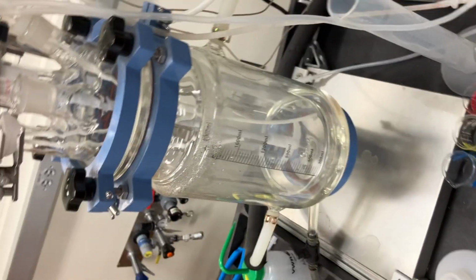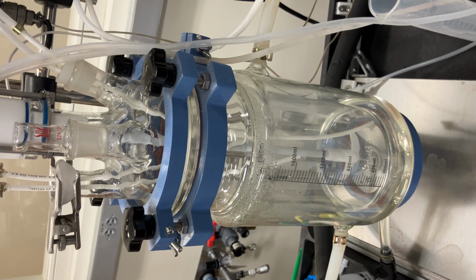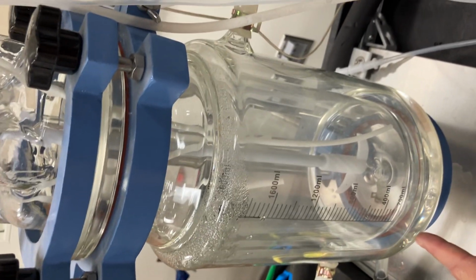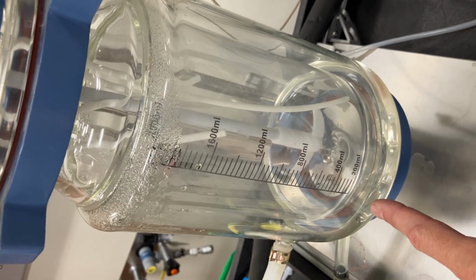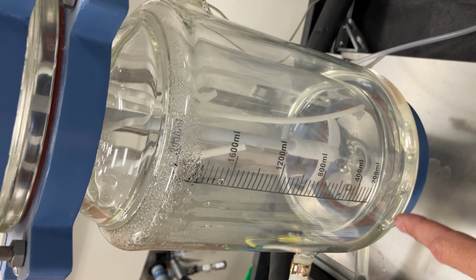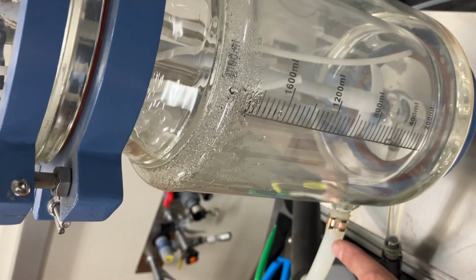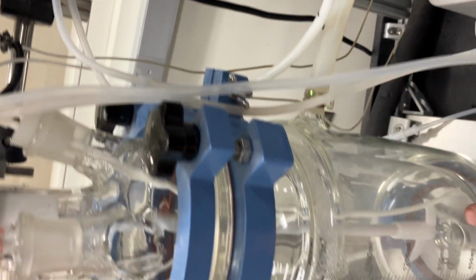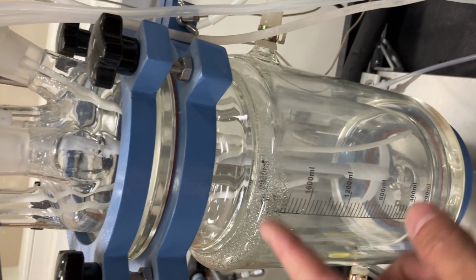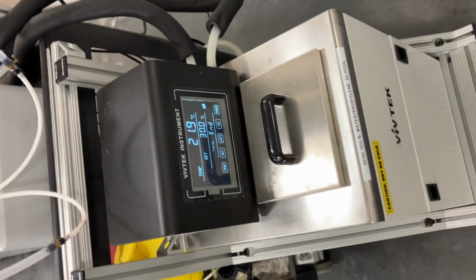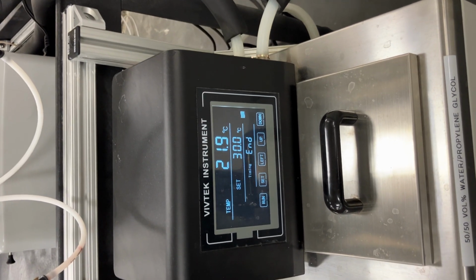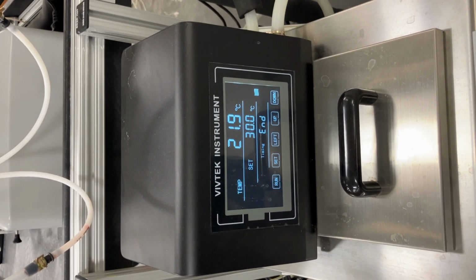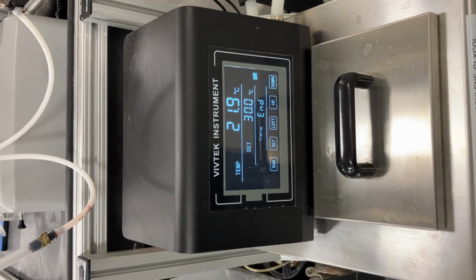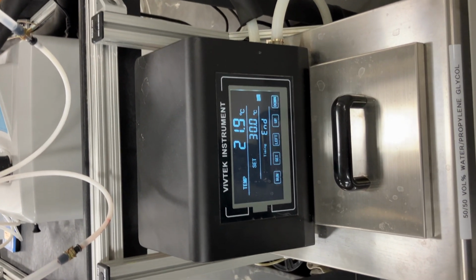There's a jacket on the reactor so you can use different temperatures. It's kind of hard to see, but there is a little bit of fluid down here of the heat transfer fluid. That's propylene glycol and water. As you pump it in on these ports here and then up and out over here, it's going to fill the jacket with that heat transfer fluid and run over here to the heat exchanger or chiller. And you can set this to different temperatures. Right now it's set to 30 degrees and its current temperature is 21, and you can hit the run button and it will heat up the fluid to 30 degrees, which will heat the reactor.